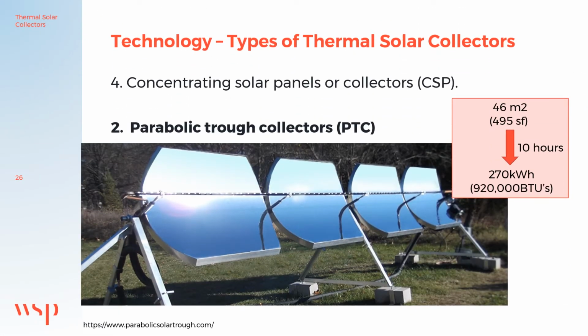This is an example of a small PTC with a footprint of 46 square meters or 495 square feet. It can collect approximately 270 kilowatt hours or 920,000 BTUs on a clear day using 10 hours of sunlight. There is a water tube running in the center, and the length of the trough is the focus point of the solar radiation. Water is pumped through the receiver tube and is heated as it passes through the tube.